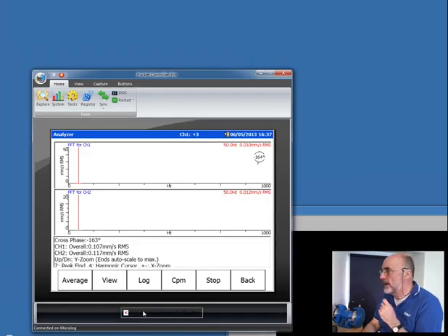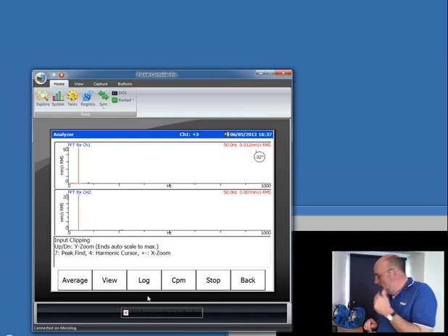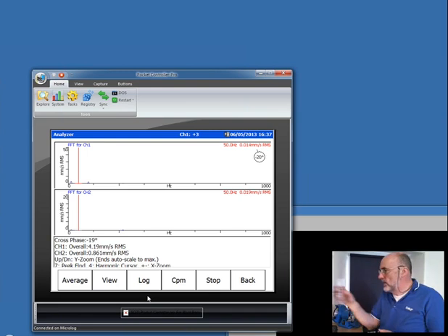I can give you a spectrum that looks like misalignment. So I'm going to cheat slightly. I'm going to put my transducer on the tool post and see if I can get you a high 2 times. So running up the machine. Give me time for a slurp of water.